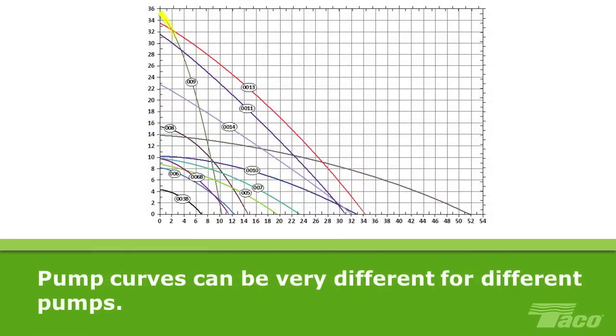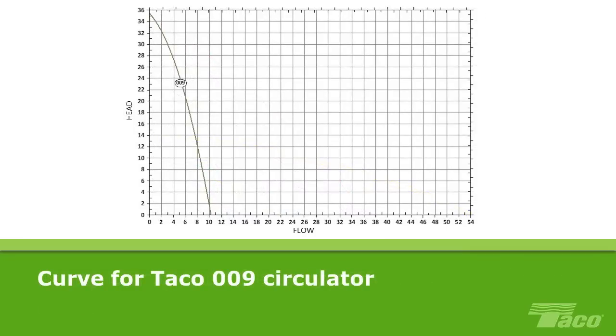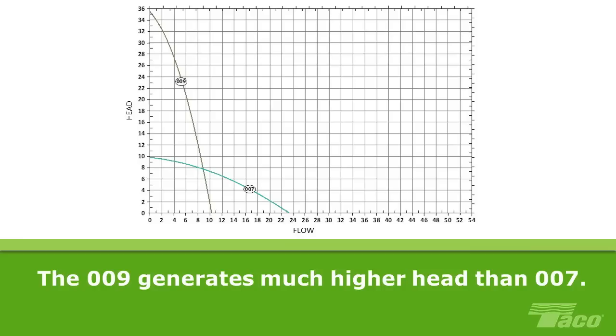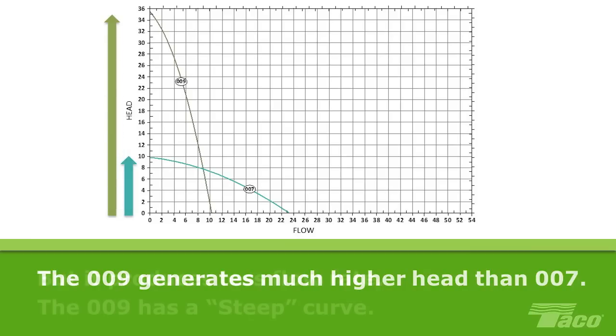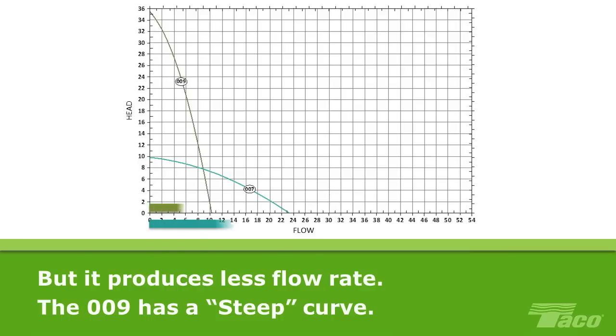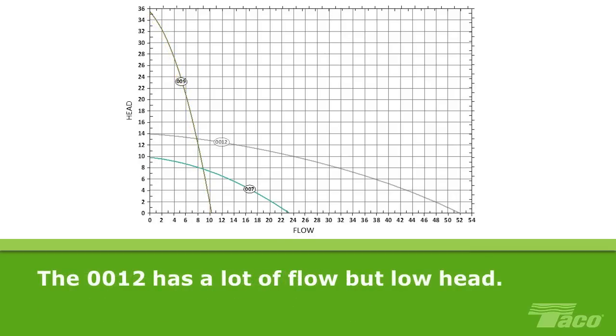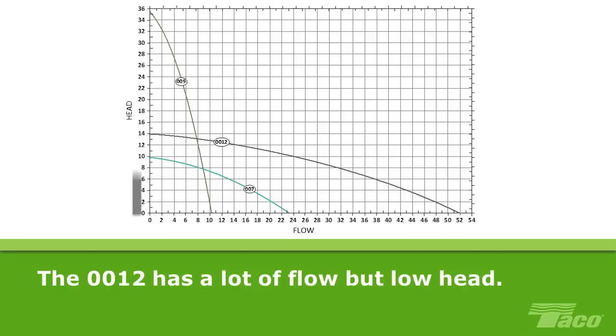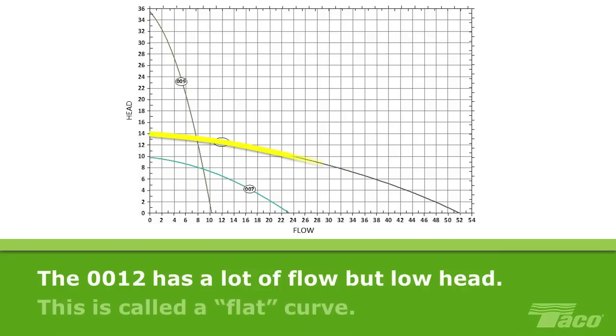As you can see on the graph, pump curves can be very different for different pumps. The Taco 009 circulator can generate much higher head than the 007 — up to approximately 35 feet of head — but it can only produce a flow rate of just about 10 gallons per minute. We say the curve for the 009 circulator is a steep curve. The 0012, by contrast, has a very different shaped curve: it can produce a lot of flow, up to 52 GPM, but a maximum of only 14 feet of head pressure. We call this a flat pump curve.